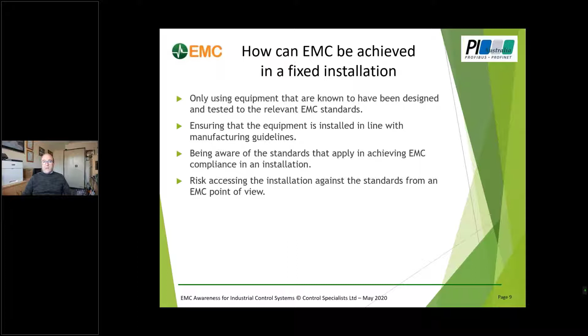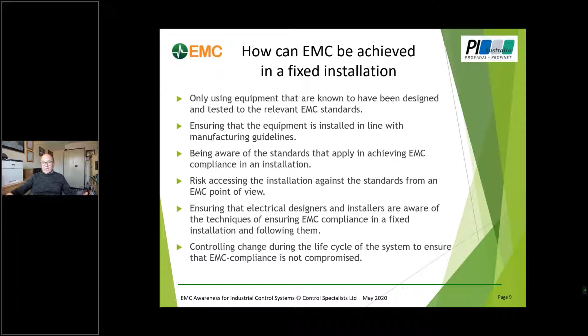Ensuring that the electrical designers and installers are aware of the techniques for ensuring compliance in this fixed installation, and also follow them. Then, probably more importantly, and aimed more at the end users here, managing change during the life cycle of a system. If somebody runs an extra length of cable in an area that wasn't there before, or adds a drive that wasn't there before, the implications need to be considered to make sure the EMC compliance you presumably had isn't compromised.